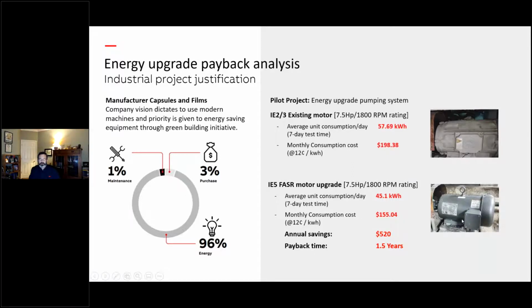And then they measured the FASR motor, and it dropped to 45 kilowatts, which equated to, at their cost of 12 cents a kilowatt hour, $155. So that's $520 in savings, and it was a year-and-a-half payback. And that was just one motor, one 7.5 horsepower motor. So even going variable speed to variable speed, swapping out the motor, you can see some significant energy savings and get into that magic sweet spot where everybody wants to be under 2 years from a payback analysis standpoint. So I wanted to show these because it's real world information, real world data, not lab data. It just shows what we've been talking about here.